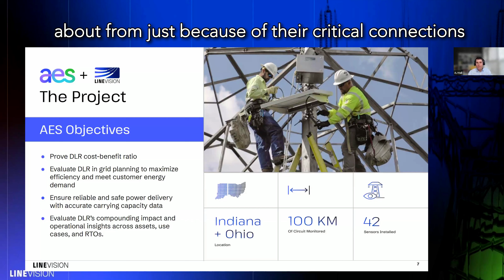LineVision performed line profiling studies, looking at the geography of the line, heading changes, historical wind speeds, and all the factors that go into estimating DLR performance on these lines—essentially, what potential capacity increases could be achieved. You also have to take into account other limiting elements besides the transmission line itself; for instance, a wave trap or relay in a substation might also need upgrading to achieve a higher rating.